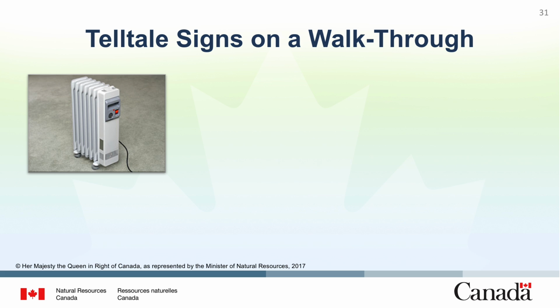This indicates that something's wrong with the facility that requires high-intensity electric space heaters. So what could have changed? Have the control sequences changed on the air conditioning systems? Or maybe the seals are bad on the windows and doors and there's too much air coming in causing drafts. These are the types of questions we need to be asking ourselves.